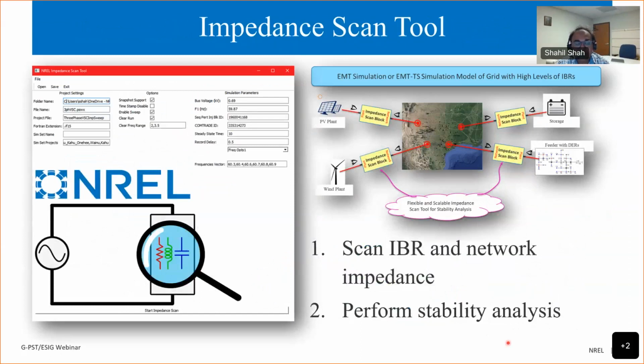To apply this approach, we have developed a software tool over the last 4 years. We call it simply the impedance scan tool. On the left, you see a graphical user interface for this tool, and it interfaces with these yellow boxes. This software is based on the PSCAD EMT simulation tool. These yellow boxes are what reside in the PSCAD model, and the GUI interacts with them. For example, if I want to understand how this PV plant impacts the oscillation modes of a system, then I insert this yellow box between the plant and the grid.